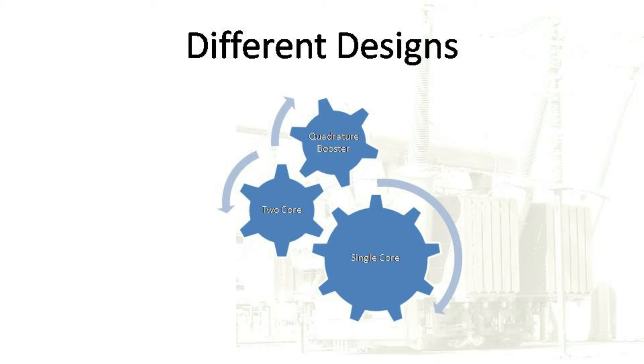Starting with the simplest one — the single core design — simplicity and cost are benefits of this particular architecture. However, there are problems with this design as well. The tap changer is usually linked to the system and is generally vulnerable to overvoltages directly caused by faults. The voltage per tap changer step and the current is determined by the specifications and does not always allow the tap changer to make an optimum economical choice. Additionally, the phase shifting transformer short circuit impedance usually varies and can go from a maximum value to zero, meaning it cannot be anticipated as to how effectively it will reduce fault currents within the system.